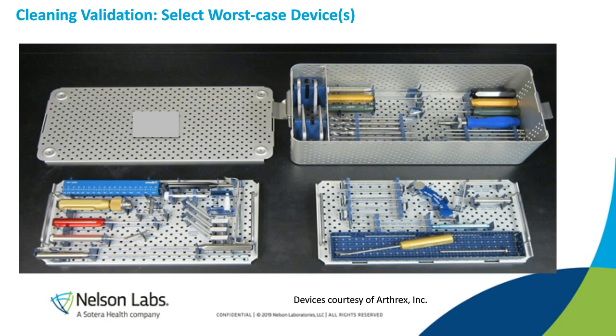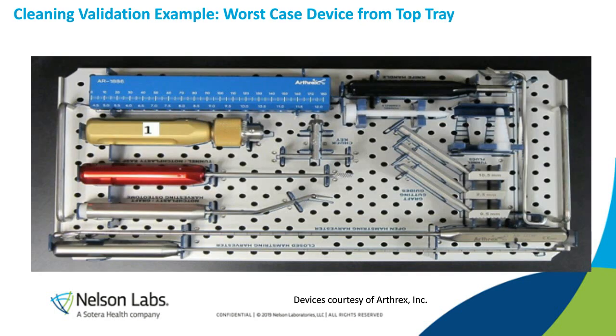Here's a close-up of one of the trays. This is the top tray of the tray of devices, and the gold device that has a 1 on it is what would be determined as the worst case device, since it is a ratcheting handle that includes a dead end lumen, and it also includes some knurled area at the top part and a lot of inaccessible areas of the device.